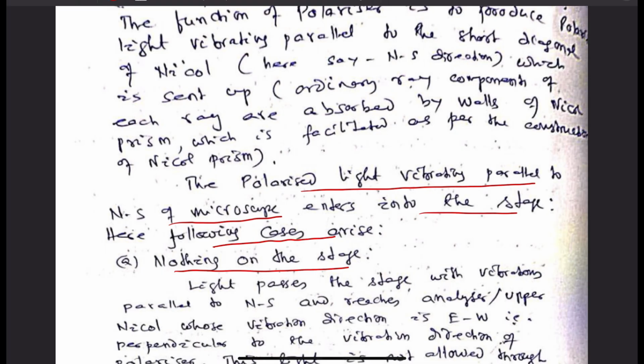To test that, we need to keep nothing on the stage of the microscope and then see, when both analyzer and polarizer are in use, whether their vibration directions are mutually perpendicular or not. If they are mutually perpendicular, the microscope is in perfect condition to be used for the study of optical properties of rocks and minerals.